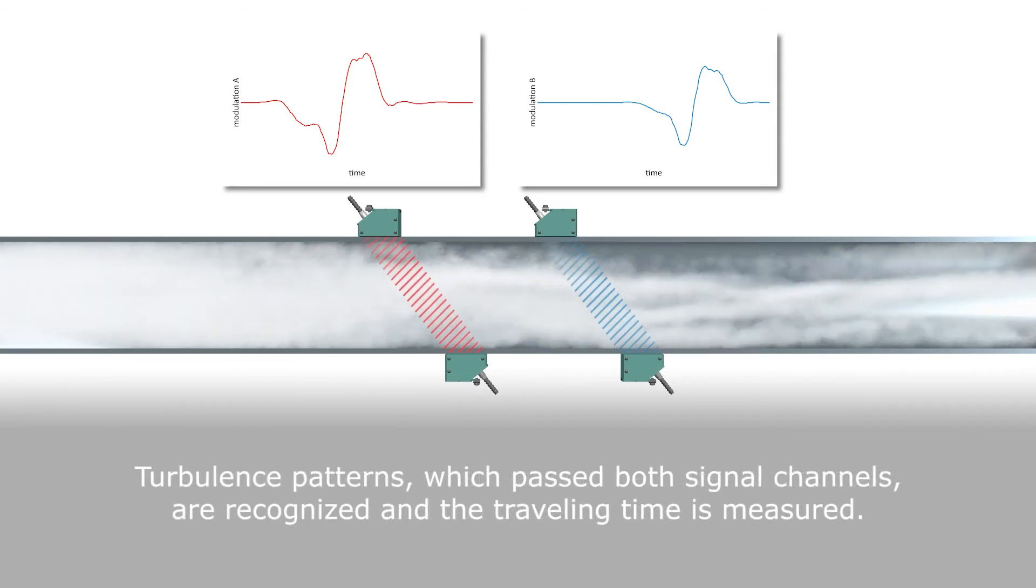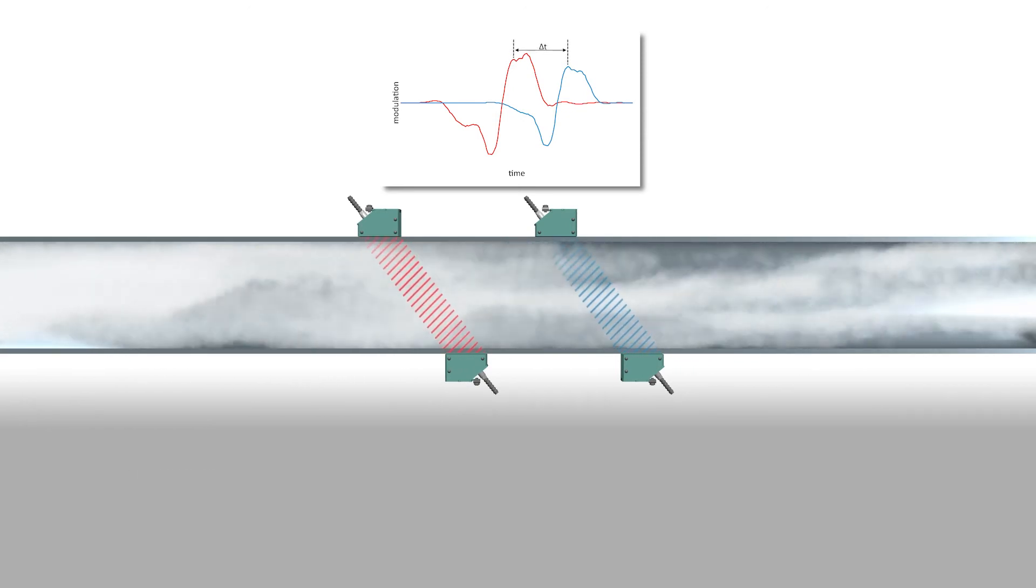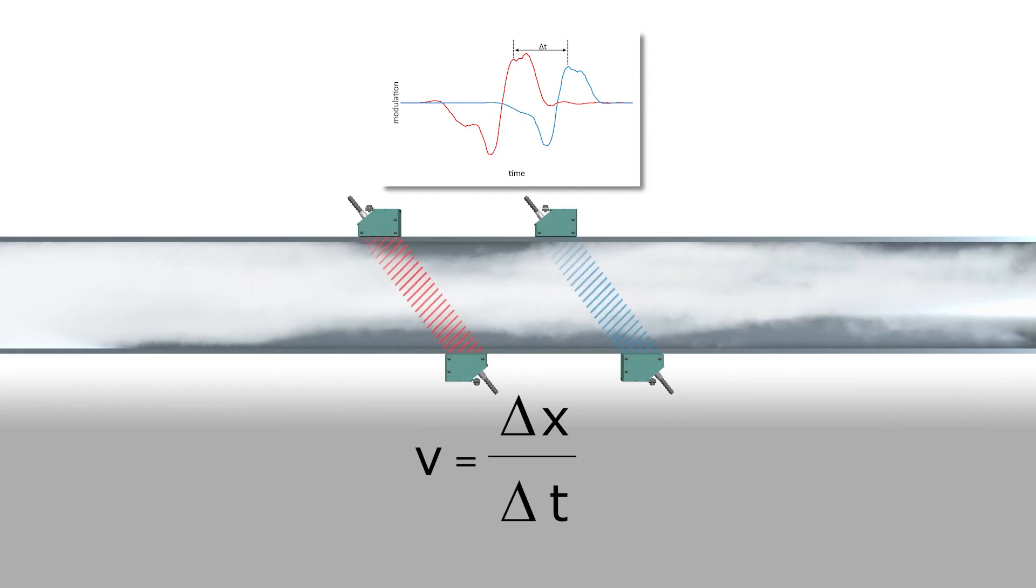The time it took for the specific turbulence pattern to pass from channel A through channel B can be found from the time difference Delta T. The equation for flow velocity calculated by the time difference and channel distance may be visualized with this equation.